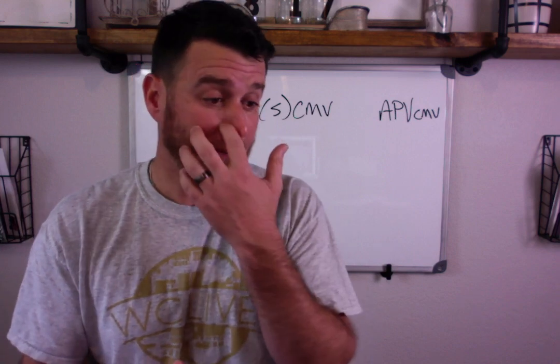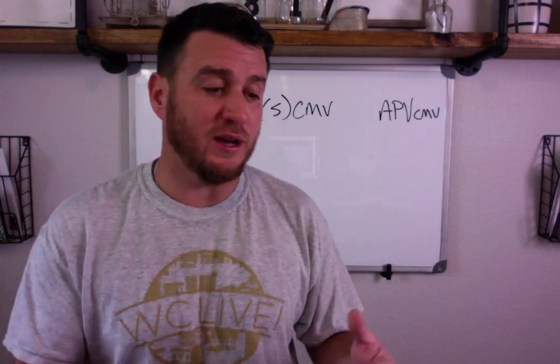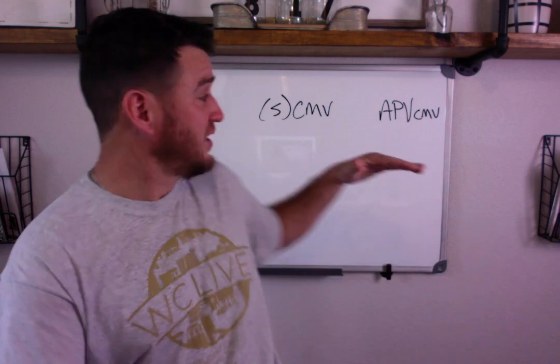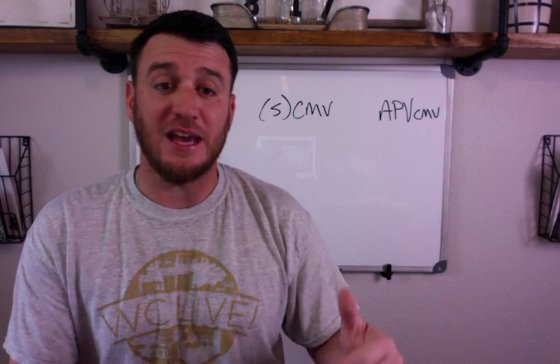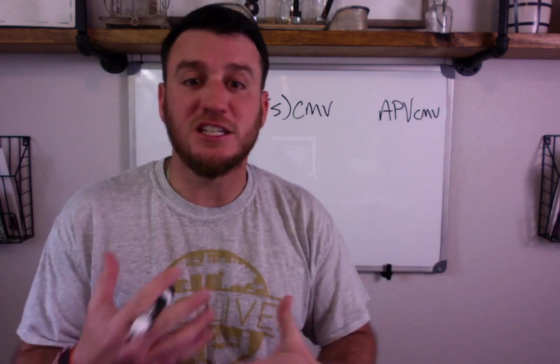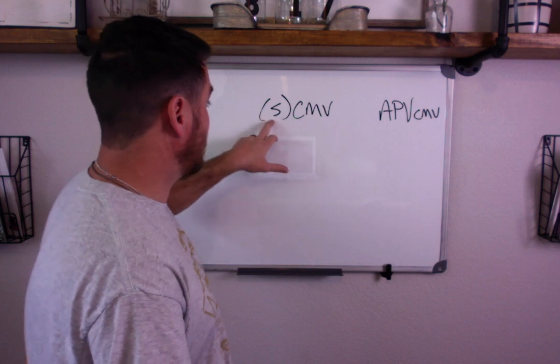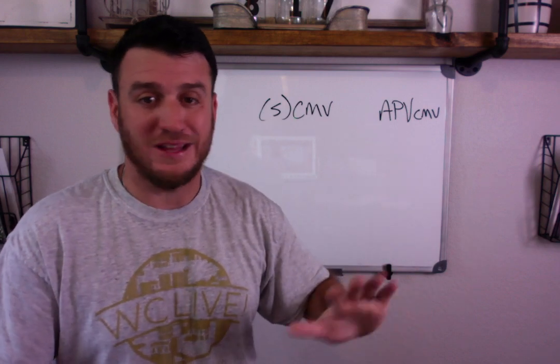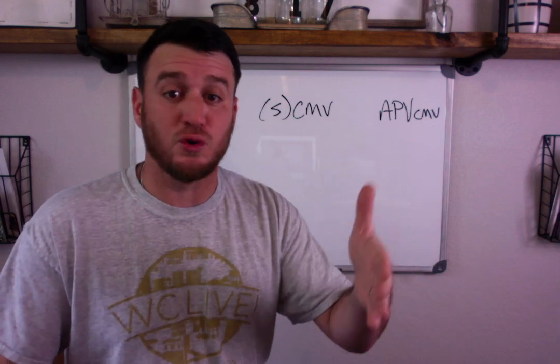This question is a prime example of that. When you ask about these modes, you're probably talking about the Hamilton G5, maybe the C3 — nomenclature that is very specific to that ventilator. If someone said put the patient in SCMV and you had no idea, you'd need to know what that mode does. SCMV stands for Synchronized Controlled Mandatory Ventilation.